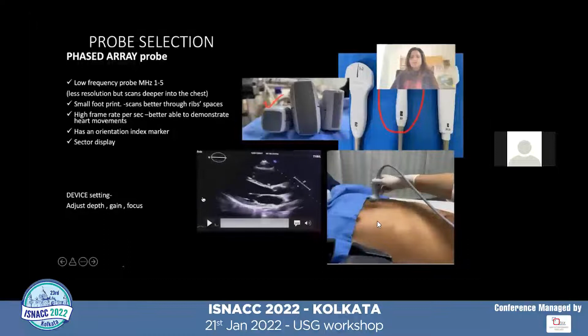It has an orientation marker on one side that corresponds to the screen marker on the right side for all the cardiac applications. The display with this probe is sectoral, as the piezoelectric crystals are focused in the center of this footprint. Once you start scanning, you have to adjust the device settings like depth, gain, and focus to get the best possible image.